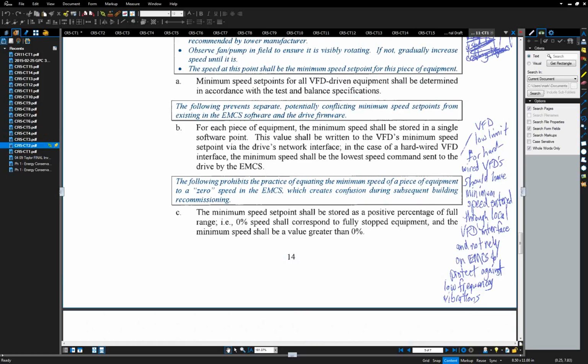VFD low limit for hardwired variable speed drives should have minimum speed entered through local VFD interface and not rely on the EMCS. Protect against low frequency vibrations. Yeah, I saw another comment about that earlier, and I guess I would say that I don't know that this necessarily has to stay as a comment. Then you were talking about using 10% or so and not having problems and so forth.